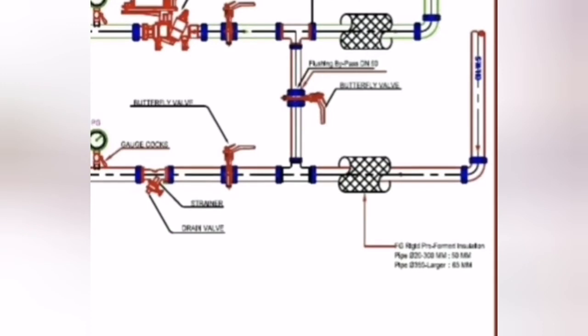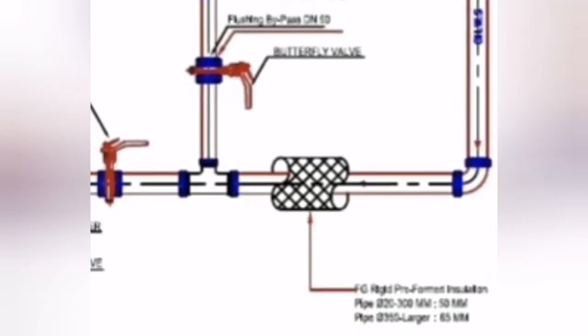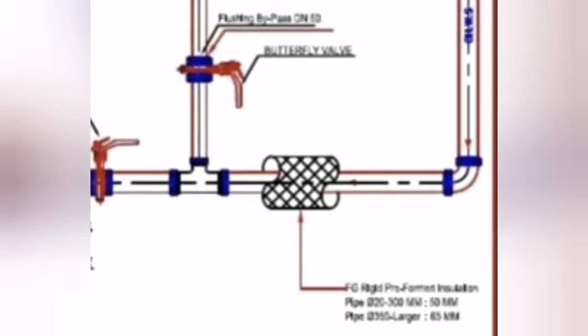Here we will start from the suction line. This red one is the suction line, on which insulation is installed. The insulation is 50 mm thick. If it's in an outside environment, it may be above 50 mm, depending on the condition of the area.